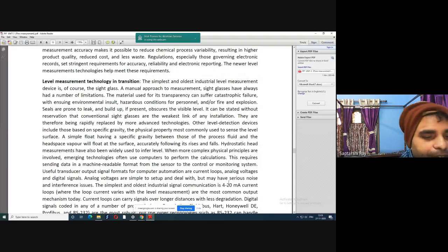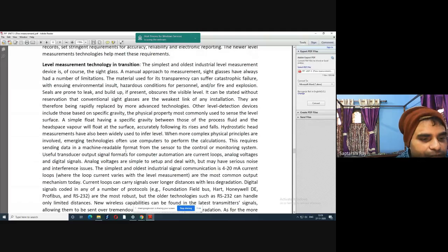Analog voltages are simple to set up and deal with, but have serious noise and interference issues. The simplest and oldest industrial signal communication is the 4 to 20 milliampere current loop, where the loop current varies with level measurement, and it is the most common output mechanism today. Current loops can carry signals over longer distances with less degradation. Digital signals are coded in any of a number of protocols, for example Foundation Fieldbus, HART, Honeywell DE, Profibus, and RS-232.